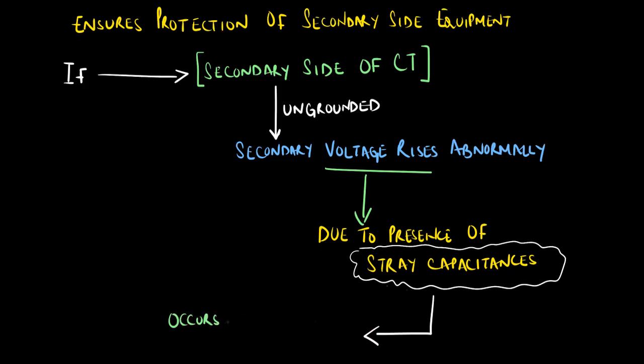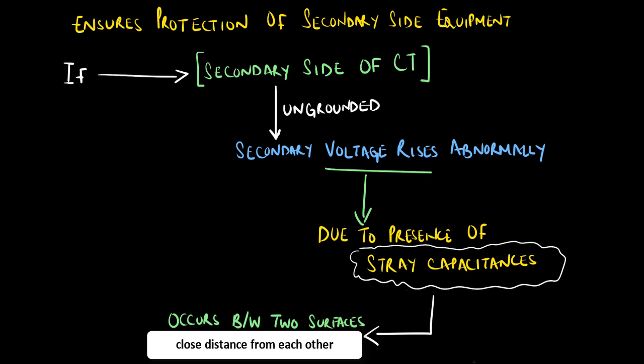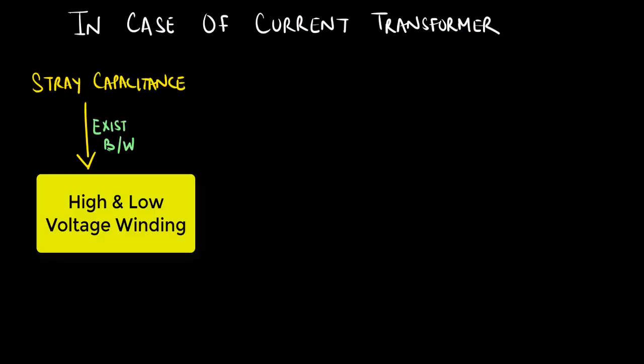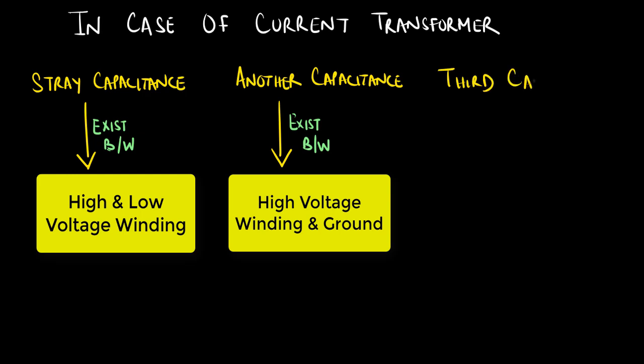In basic terms, these capacitances can occur between any two surfaces at a close distance from each other. In the case of a current transformer, a stray capacitance exists between the high voltage and the low voltage winding, another capacitance exists between the high voltage winding and the ground, and a third capacitance will occur between the low voltage winding and the ground.